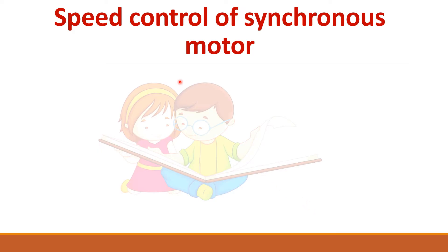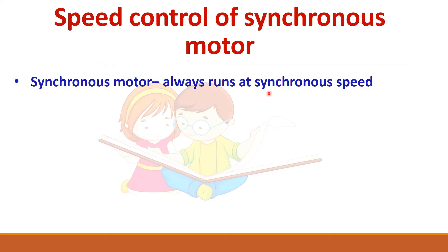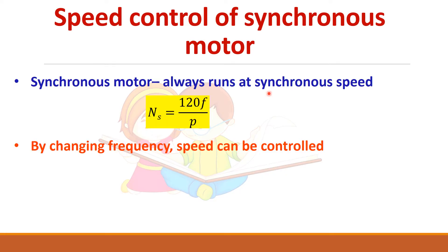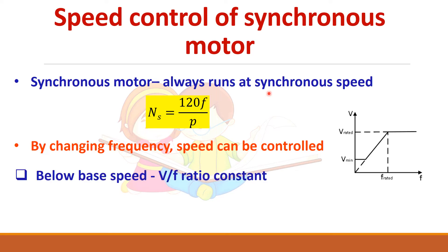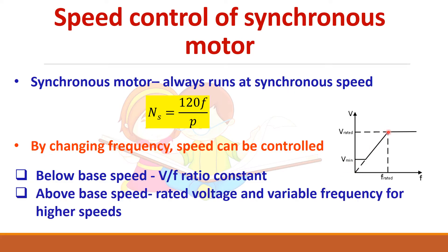The synchronous motor always runs at synchronous speed given by 120F by P, so speed can be controlled by changing the frequency. For below base speed, we keep the V by F ratio constant. For above base speed, the voltage has reached its rated value and we cannot increase it further, as that would cause insulation damage. So above base speed, it is necessary to maintain the rated voltage while increasing the frequency — that is, rated voltage and variable frequency is applied.